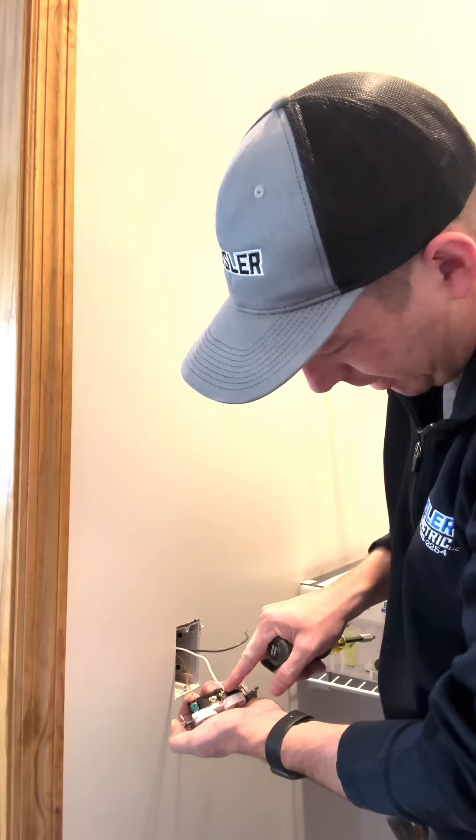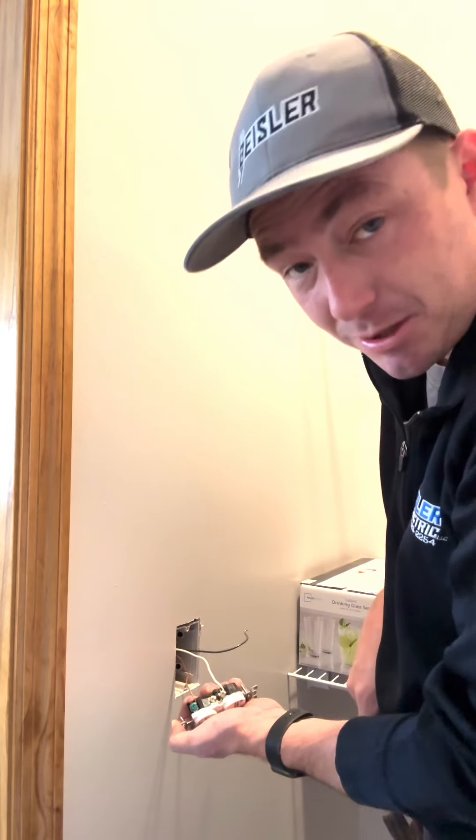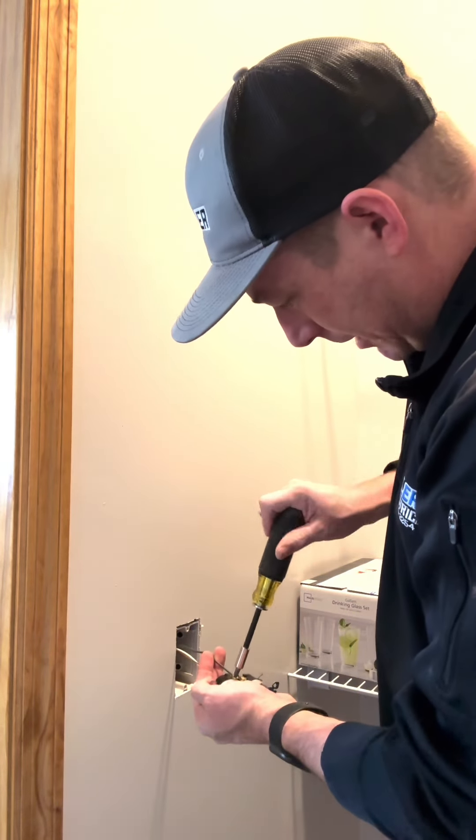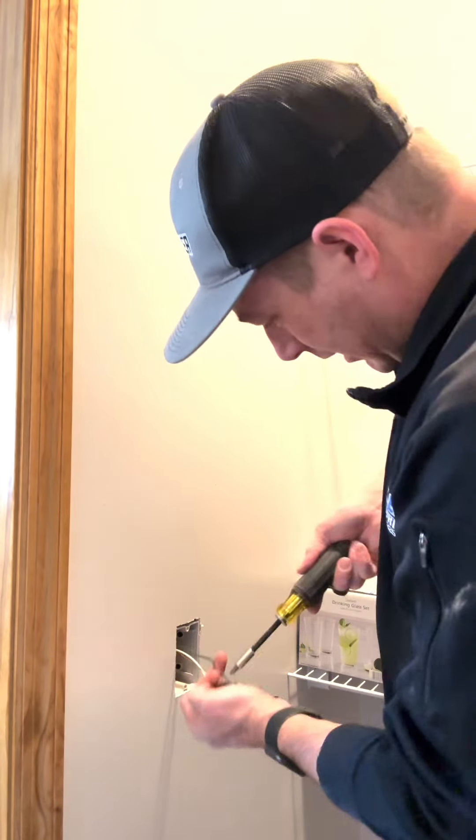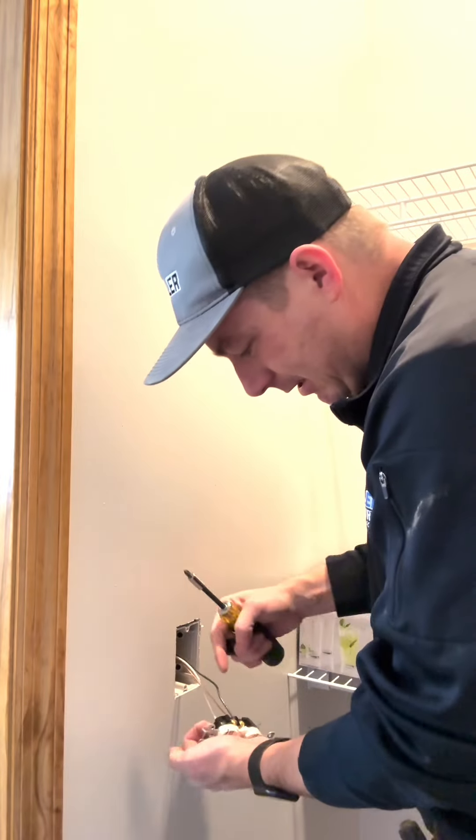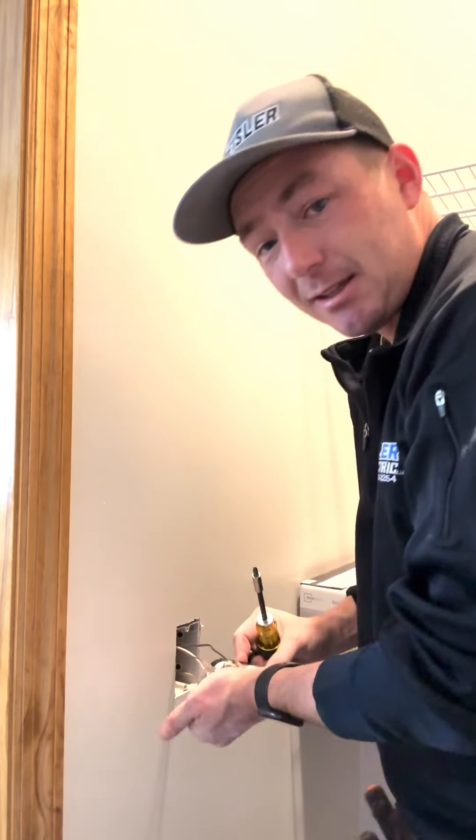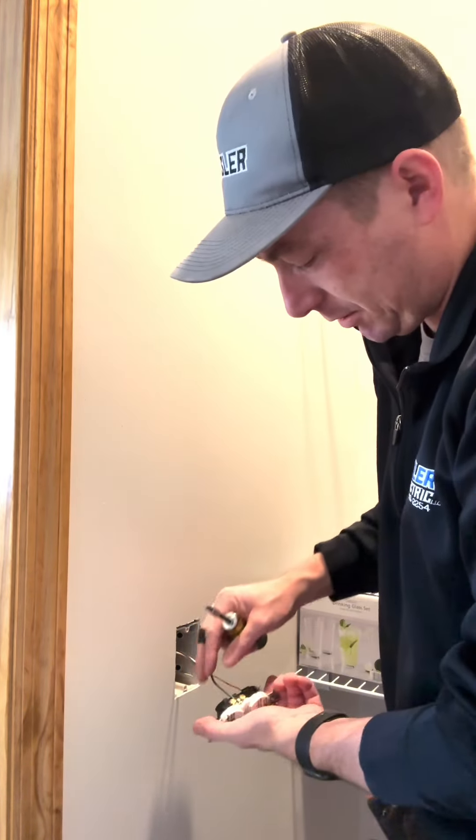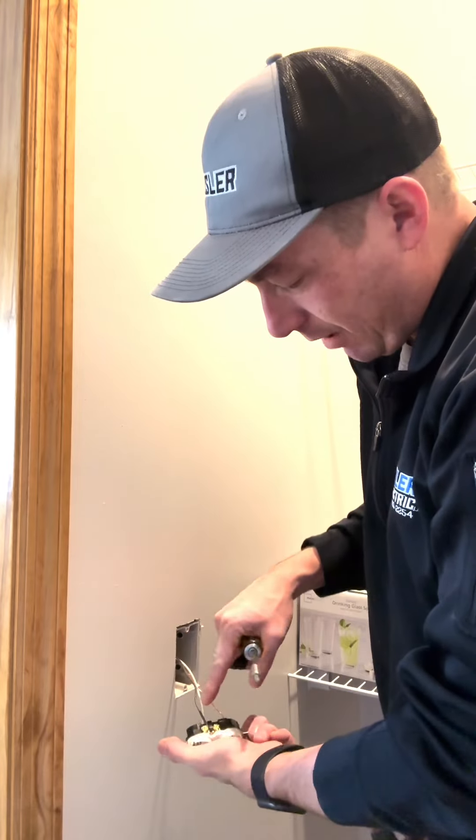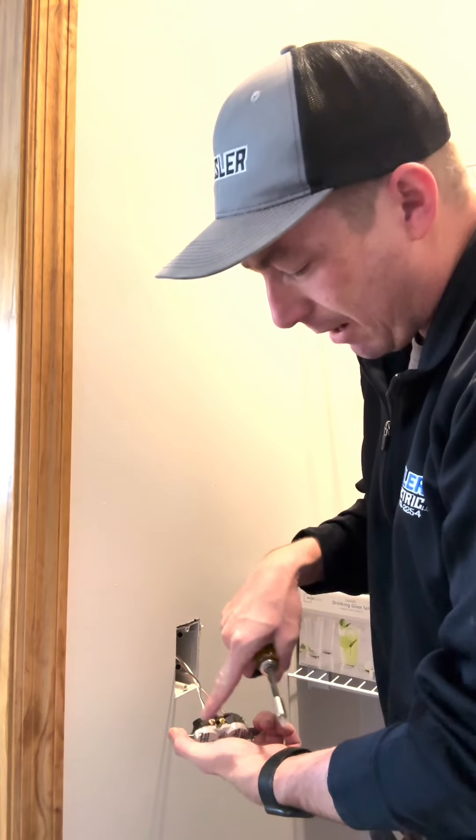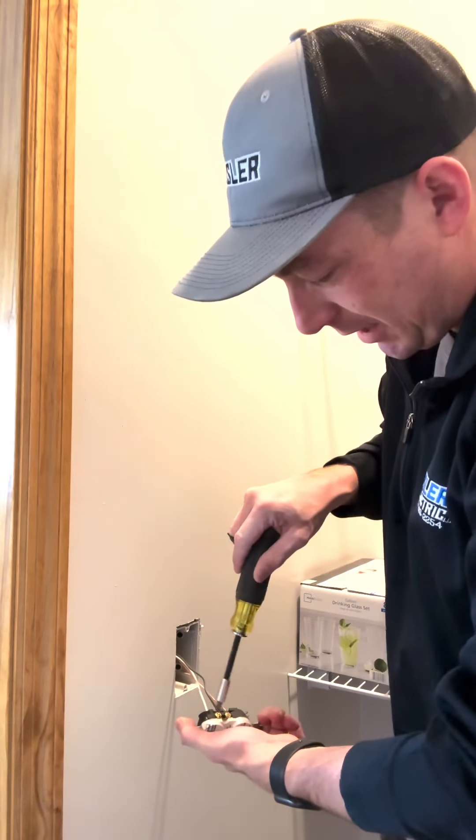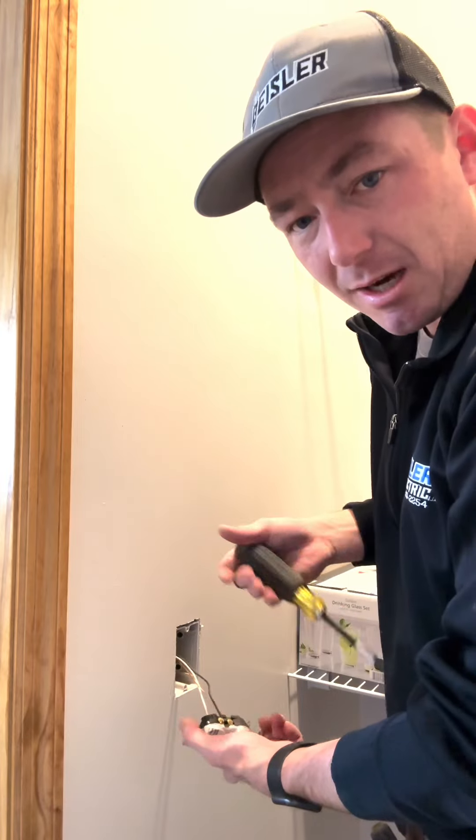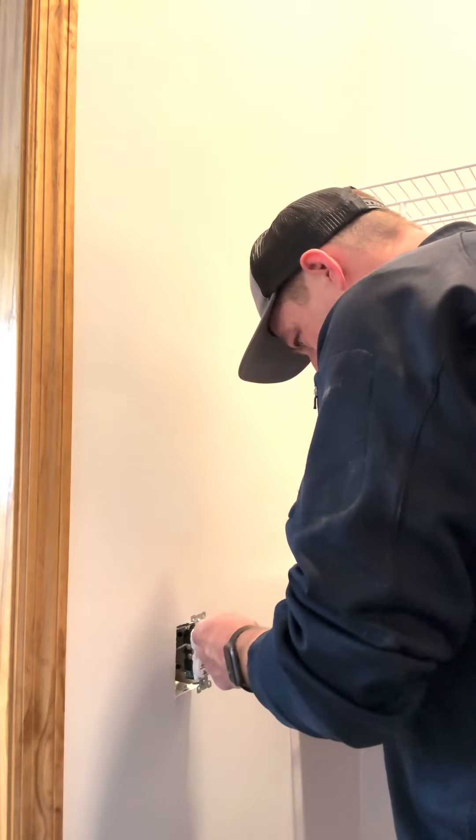Another thing when you're wrapping these wires: I'm not an advocate of stabbing the back of these outlets because it's not a good connection. So always wrap around the screws. When you're wrapping these, always wrap it around as it tightens, so don't go the other way because it could loosen that connection a little bit.